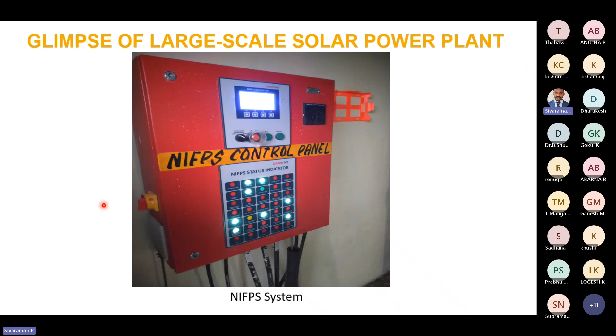Then this is the NIFPS system control panel, and this is the substation. For a large utility scale power plant, there will be a substation to connect the solar power plant to the grid. Here you can see there is a transformer. It's a power transformer, mostly in the 100 MVA and above range. It will step up the voltage from 33 kV to 220 kV or 400 kV, and it will be connected to the transmission line. So this is generally called a substation. Here there are transformers, circuit breakers, CT, PT, current transformer, potential transformer.